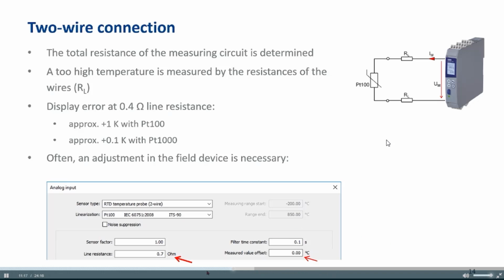If you look carefully, here you compensate the offset which comes from the core resistance. But you can work a second time and define an offset. Now, how can we consider this? Let's say we define the ohmic value, and then theoretically you have no offset coming from the wires. Then maybe you make a calibration and find out that the temperature probe has a little offset, or maybe the position is not perfect and you need to give one more offset, and this is the offset which we define here. So we distinguish two offsets: one compensates the offset coming from the cable resistance, and the other comes from an inaccuracy of other conditions.